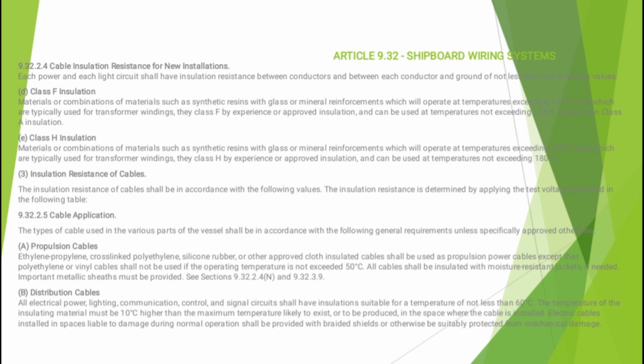For propulsion cables, ethylene propylene, cross-linked, silicone rubber, or approved cloth insulated cables are used, except that polyethylene cables cannot be used if the operating temperature exceeds 50 degrees Celsius. Moisture-resistant jacket and metallic sheath are required. Distribution cables must have insulation suitable for temperature not less than 60 degrees Celsius, with the insulating materials being 10 degrees Celsius higher than the maximum temperature likely to occur.